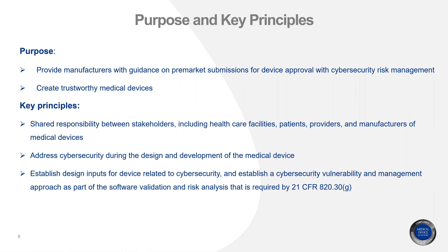Software validation must reflect your cybersecurity approach. Pre-market guidance always focuses on patient safety — safety by cybersecurity. For that reason, you identify the risk, propose security requirements, implement your mitigations, verify and validate, and document. Documentation requirements are a primary focus of this webinar. I will be discussing hazard analysis, trace matrix, and in-house controls shortly.